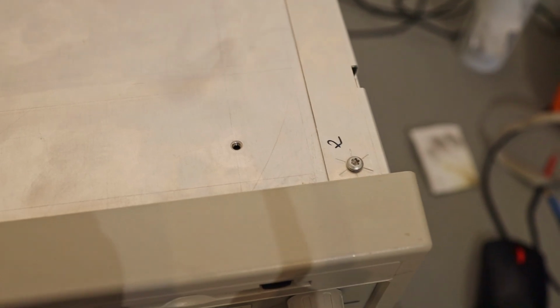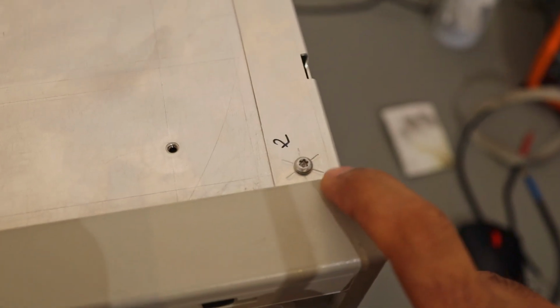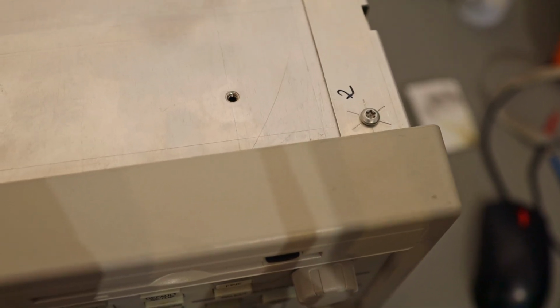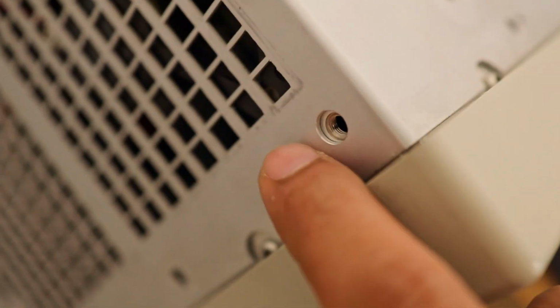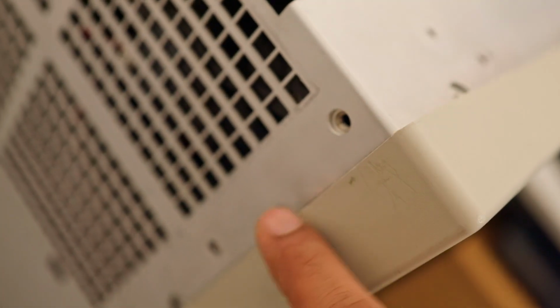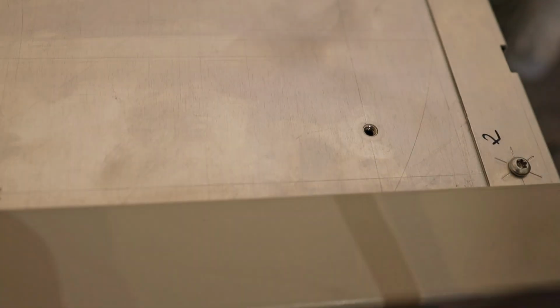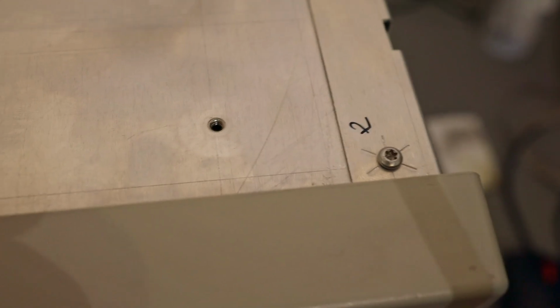So now it's the time to put it back together, and you see these star-like marks. Wherever the star-like mark goes, you have to put a screw, and if there is no star there, you don't need to put a screw there. There may be some other screw coming in. For example, you see in there is no star mark because the side panel screw will be coming there, or the rack mount screws will be coming there, and so it's very easy to not miss any screws. And for example, these places there will be a top panel and its screws will come there. So keep watch, wherever the star is, there's a screw.